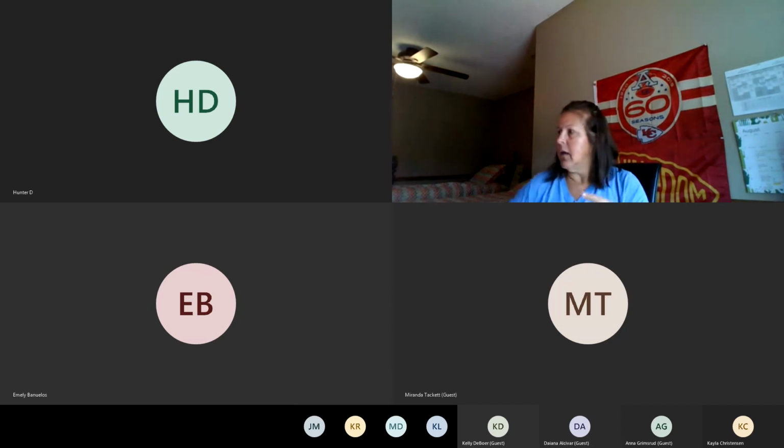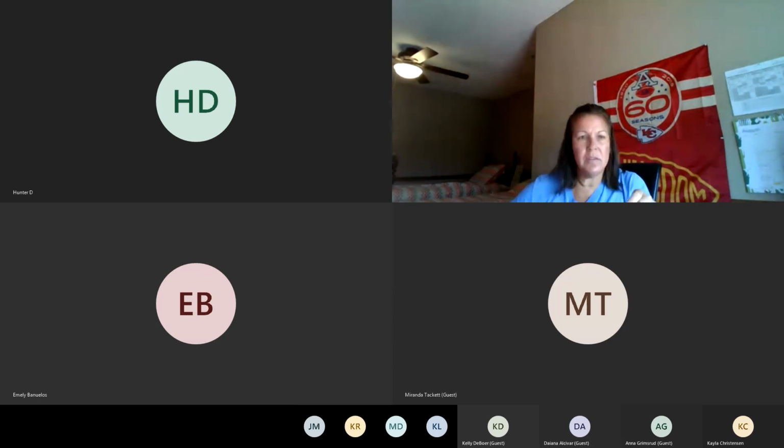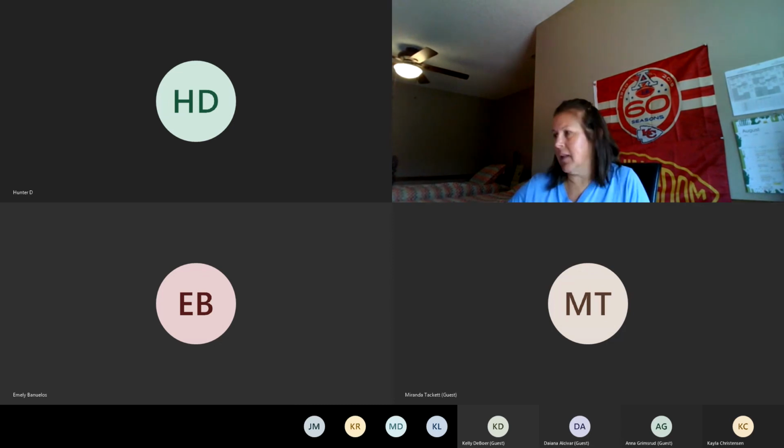you've had. These little badges need to be stored in a radiation safe zone. So you wouldn't want to store them in a room where x-rays are being taken. You don't want to store them in the sun or in the heat because that can affect them. And remember that they should always be worn at the waist level, unless, of course, like when I worked as a rad tech, I would wear the skirt and the vest. So we had to wear ours kind of out on the collar where they were exposed, because if you put them under lead, they're not going to absorb anything.